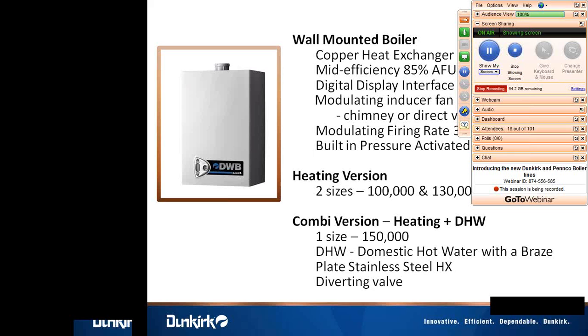But as a copper unit, it's an extremely competitively priced product, far below traditional cast iron boilers, and quite honestly, even below our Pennco product line, which is a value cast iron line. So we're very excited about this. We see a lot of possibilities in inner city applications, and certainly contractors that have been installing copper heat exchanger boilers, such as Teledyne Laars, or Lochinvar, or Raypak. Generally, they buy those boilers for price and because of overall weight, and this boiler will fit into both of those criteria. It's lightweight and it's extremely competitively priced.